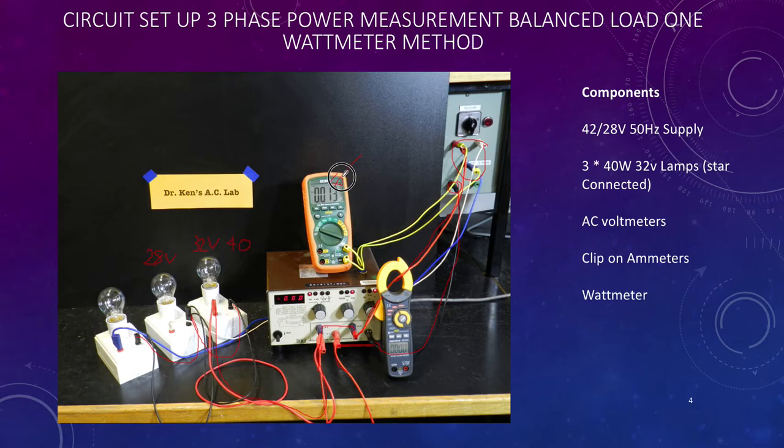We should get a line voltage, sorry phase voltage, somewhere in the order of about 28 volts. We'll see when we turn it on. So we're measuring our voltage externally, we're measuring our current here on the clip-on ammeter externally, plus we have a wattmeter also measuring. What we're going to do is compare what we get on our voltmeter and our ammeter with what gets displayed on our wattmeter. So that's the purpose of the exercise.